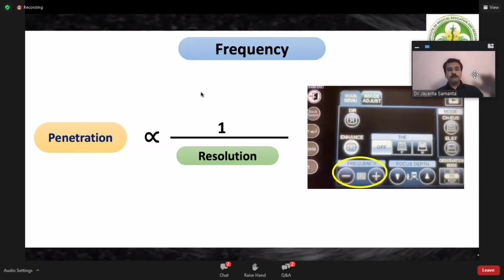We need to understand that as we go on increasing the frequency, the resolution increases, but the depth of penetration decreases. As I've already mentioned earlier, this occurs because of the phenomenon of absorption. So if we want a better resolution image, we can increase the frequency, but at the cost of penetration. Here I can show you that at 5 megahertz, we can see the further depths of the EUS image.